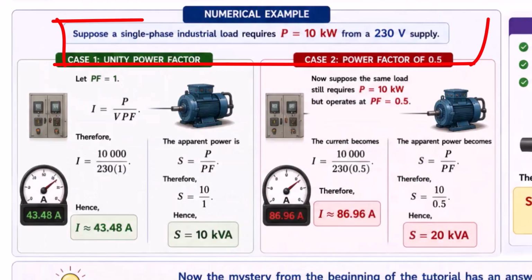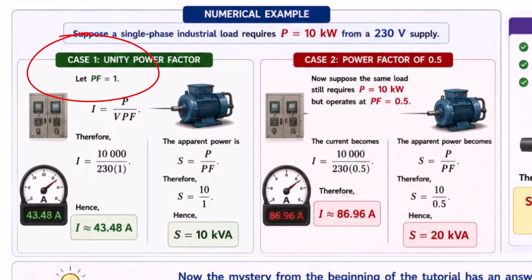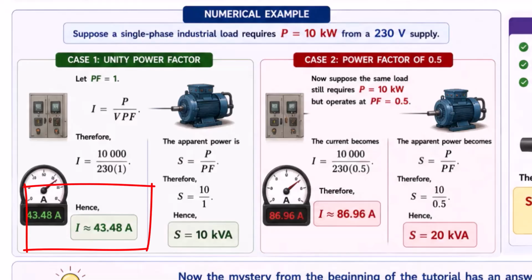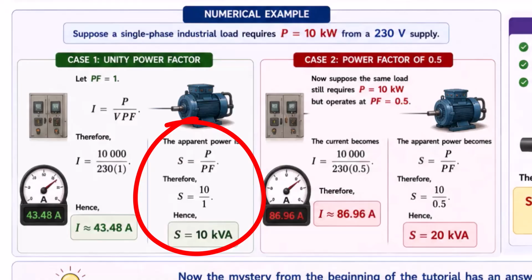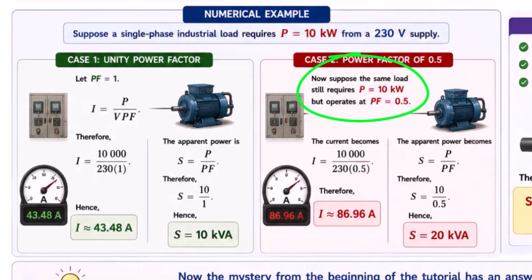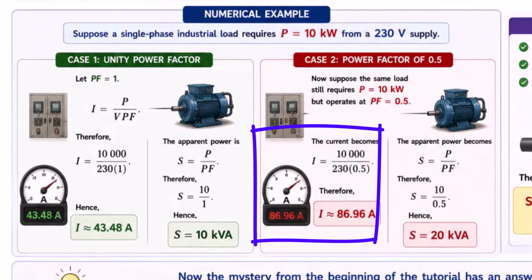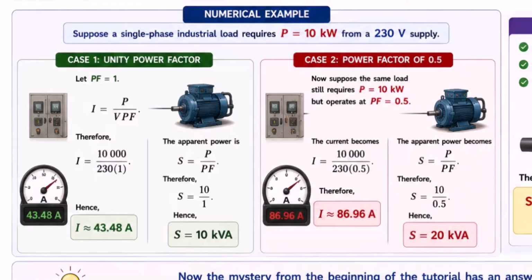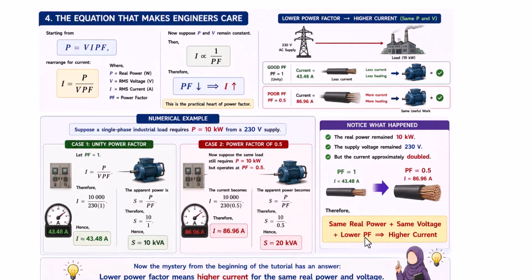Suppose a single phase industrial load requires P is equal to 10 kilowatt from a 230 volt supply. Let's consider case 1. In case of unity power factor, we obtain I is equal to 43.48 ampere and the apparent power will be 10 kilovolt ampere. In case 2, the power factor value is 0.5. P is still 10 kilowatt. If we put this value in this equation, we obtain that I is equal to 86.96 ampere and S is equal to 20 kilovolt ampere. Notice what happened. The real power remained 10 kilowatt. The supply voltage also remained 230 volt, but the current approximately doubled. Therefore, we can say that same real power plus same voltage plus lower power factor is equal to higher current.